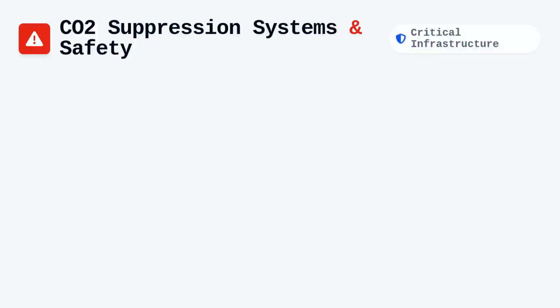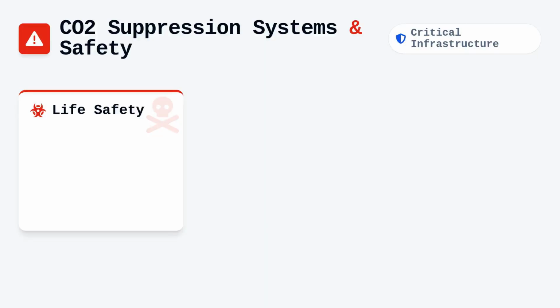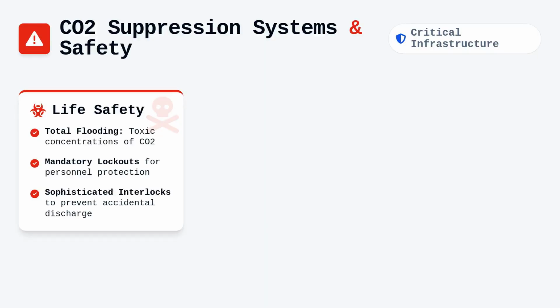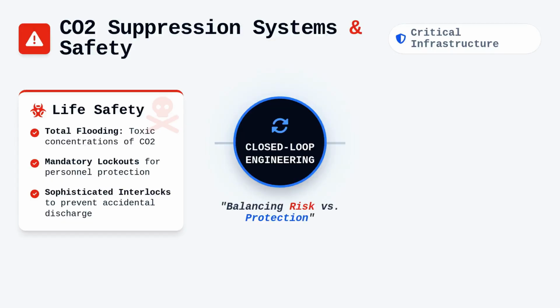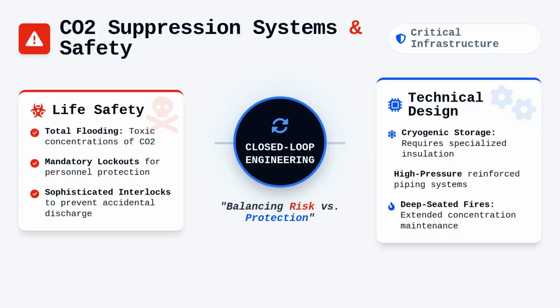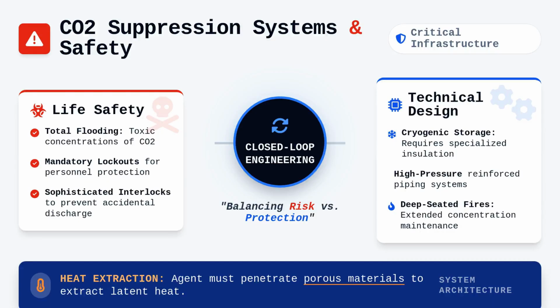Carbon dioxide suppression systems introduce a unique set of hazards because they extinguish fires by total flooding at concentrations that are inherently toxic to humans. This creates an immediate mandate for strict life safety lockouts and sophisticated interlock controls in any occupied facility. When planning CO2 systems for deep-seated fires, the design concentration must be maintained significantly longer than for surface fires, because the agent must penetrate porous materials to extract latent heat.